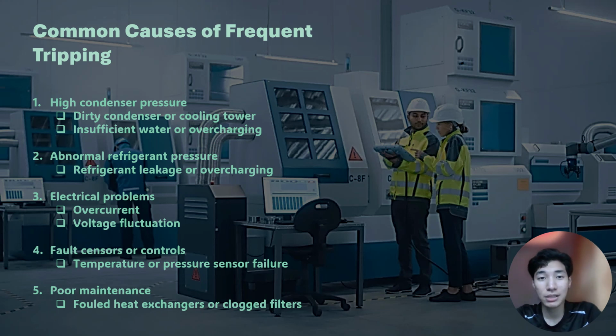Okay, next we go to the common causes of frequent tripping. First is high condenser pressure. High condenser pressure is caused by a dirty condenser or cooling tower, then insufficient water or air. Secondly is abnormal refrigerant pressure, from refrigerant leakage or overcharging. Next are electrical problems, caused by overcurrent and voltage fluctuation. Next are faulty sensors or controls, caused by temperature or pressure sensor failure. And the last one is poor maintenance, caused by faulty heat exchangers or clogged filters.